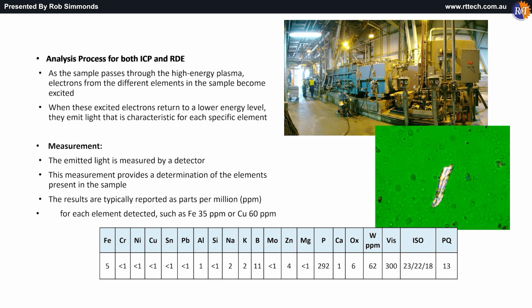Analysis process for both ICP and RDE spectrographic. As the sample passes through the high-energy plasma, electrons from the different elements in the sample become excited. When these excited electrons return to a lower energy level, they emit light that is characteristic for each specific element. The emitted light is measured by a detector. This measurement provides a determination of the elements present in the sample. The results are typically reported as parts per million, or ppm, for each element detected, such as iron at 35 ppm or copper at 60 ppm.